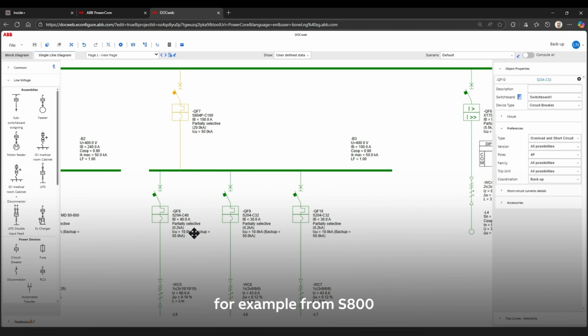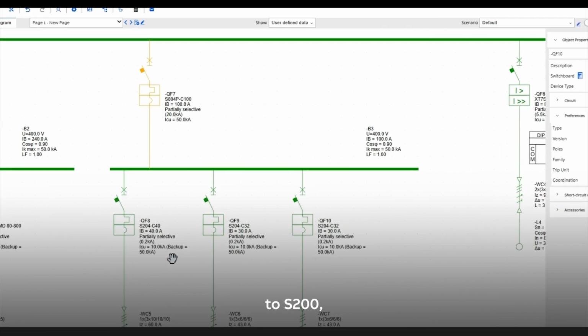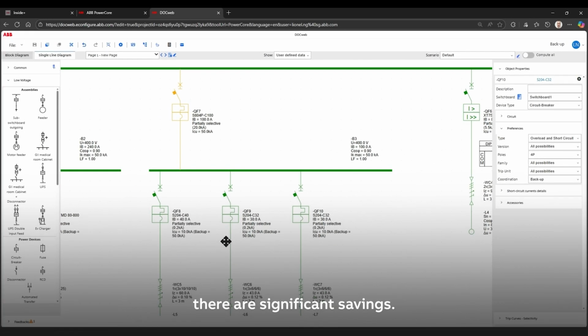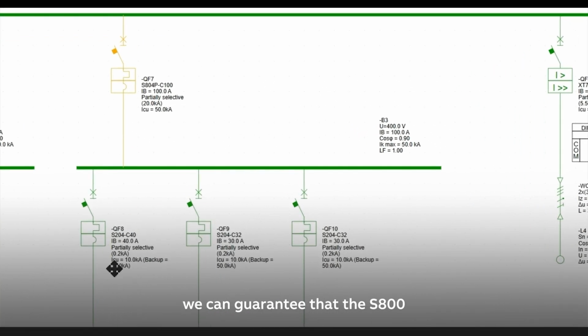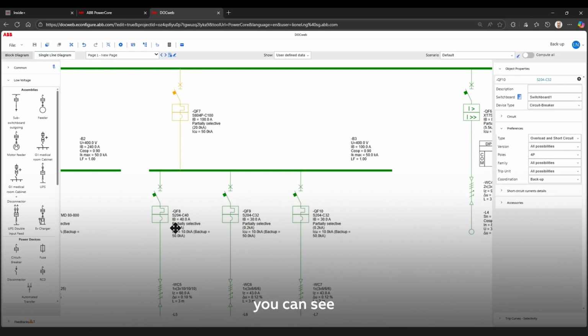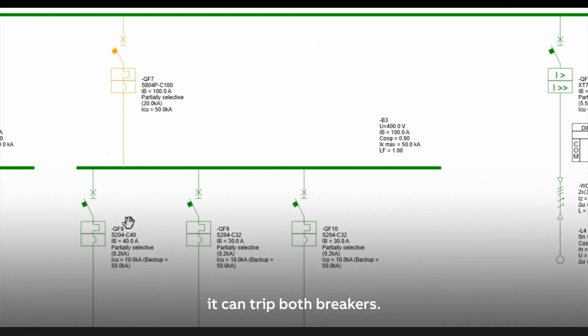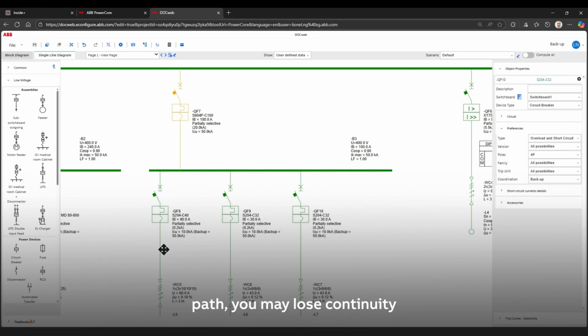For example, from S800 to S200, meaning from a 50 kiloampere breaker to a 10 kiloampere breaker, you can see there are significant savings. With this combination, we can guarantee that the S800 will back up the S200 up to 50 kiloamperes. But again, you can see the partial selectivity is around 0.2 kiloamperes. So if the fault level is higher than that, it can trip both breakers. Even if the fault is on one path, you may lose continuity to the other paths as well.